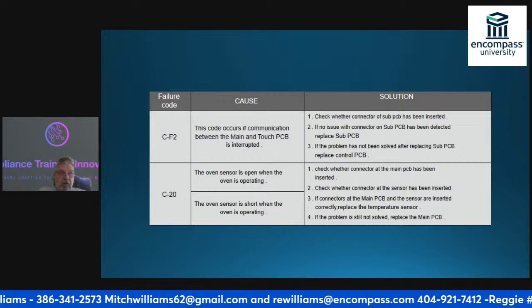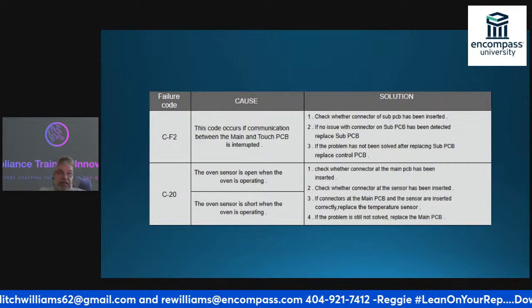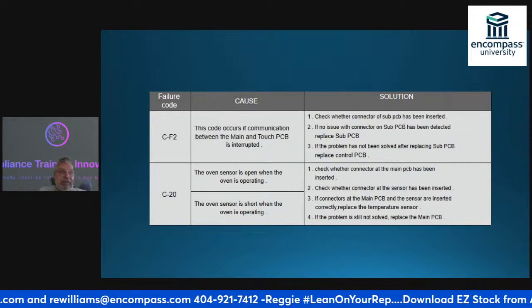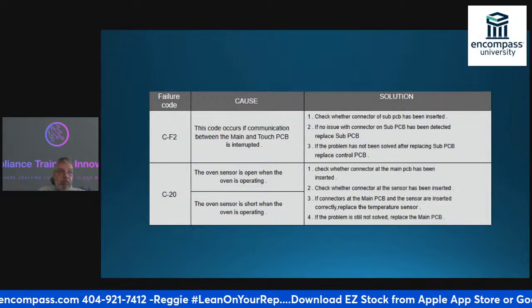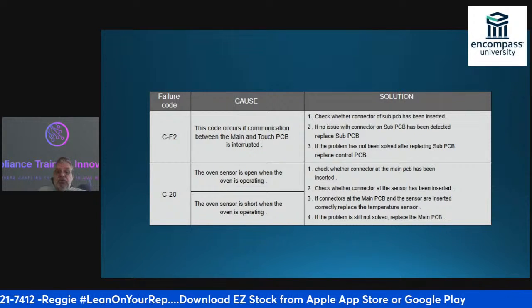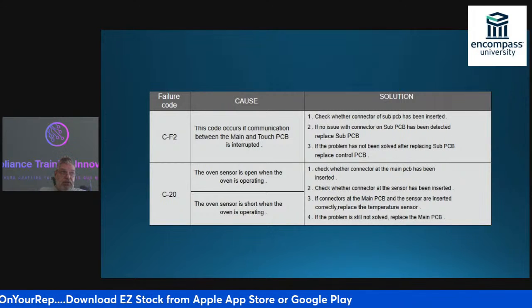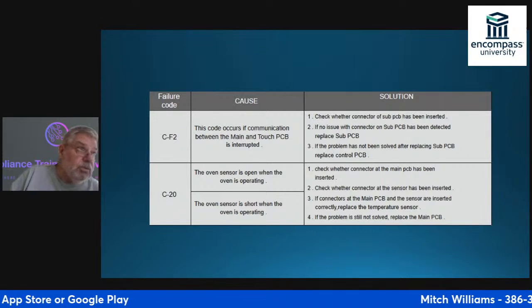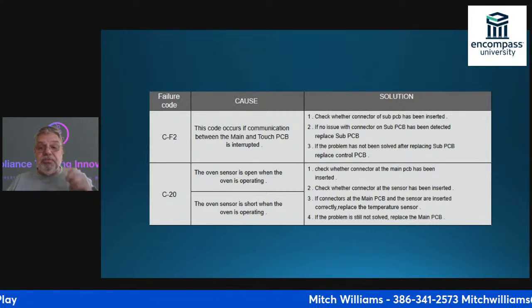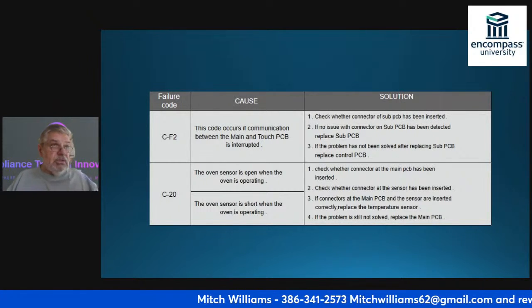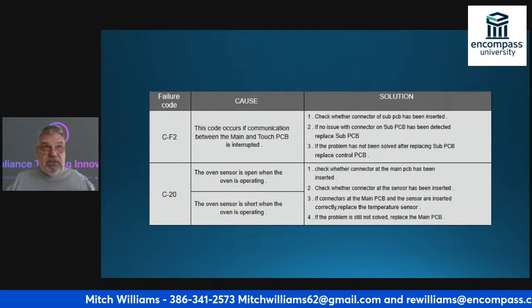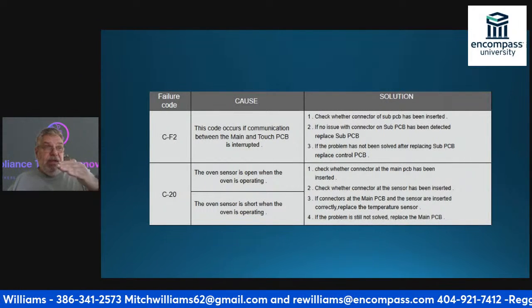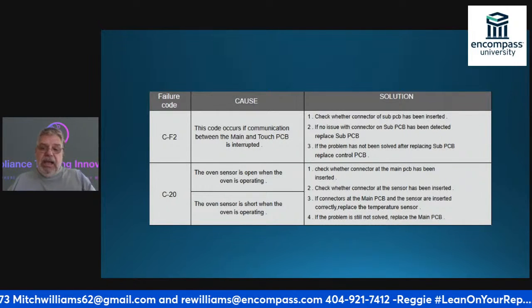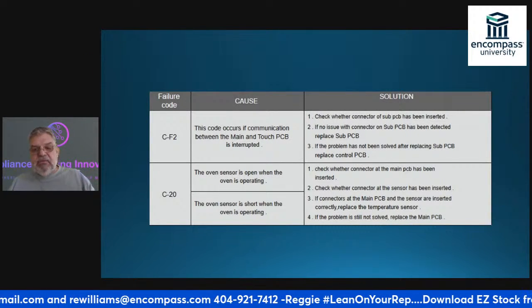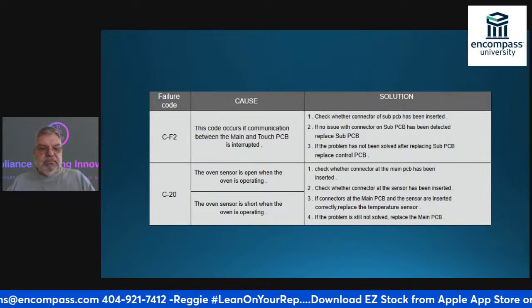If I still have a problem, usually 99 times out of 10 that fixes it. The first thing you're going to do is check your sensor, because you should be able to look at your sensor ohms, and it should tell you the resistance you should have at certain temperatures. If those are within range, I'm not going to replace the sensor, I'm going to replace the main PCB.